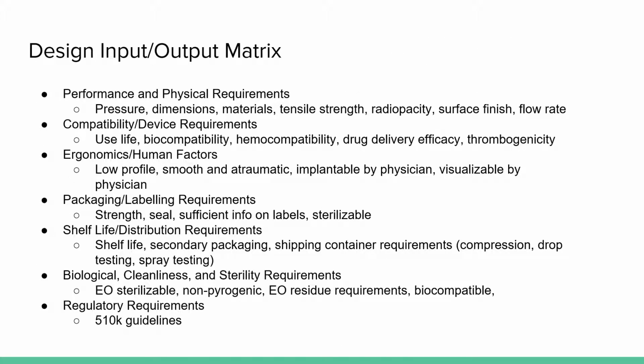So after deciding on the final design of the implant port, the team created a design input output matrix that includes the specifications to the implant port. Some requirements were given to the team, such as the device needs to withstand 50 psi and have a shelf life of 6 months, while some requirements are FDA regulated, such as the testing done for shipping containers.